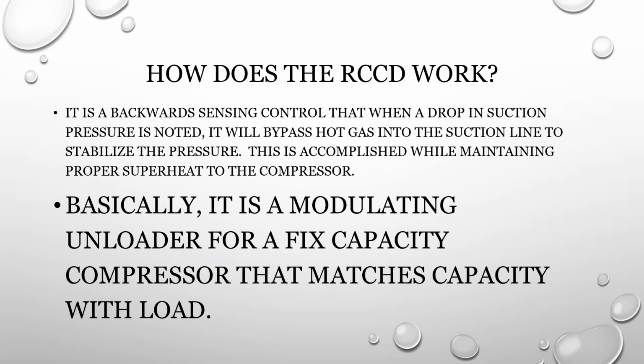This is not hot gas. Hot gas loads the evaporator. This unloads the compressor. Thus, basically, it is a modulating unloader for a fixed capacity compressor that matches the capacity with load.